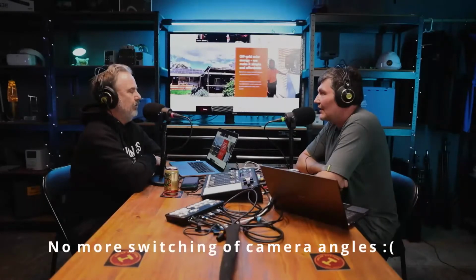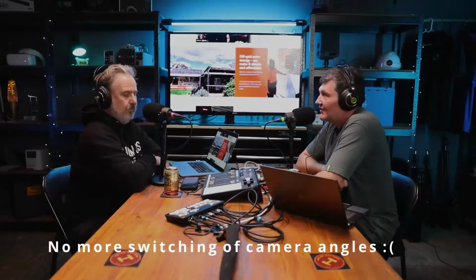And another trick on this particular system, unfortunately, you need long strings, like 11, 12 panels, not less. Minimum voltage is 330 volts of DC input. And it's actually not just like that. It's an interesting formula. It's the AC output voltage, 230 volts, multiplied by 1.44. That's the minimum DC voltage that has to be on the panel side.